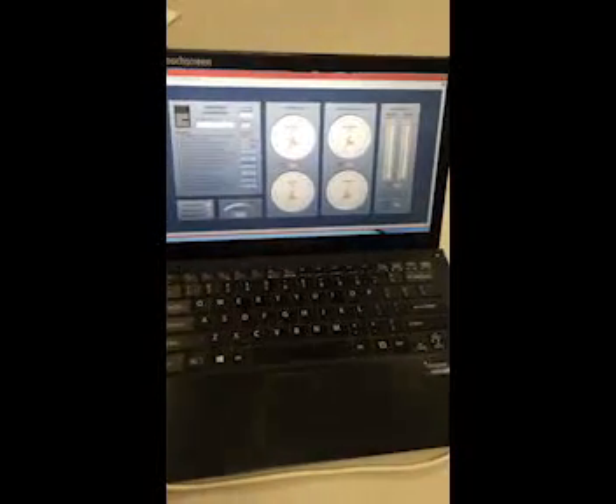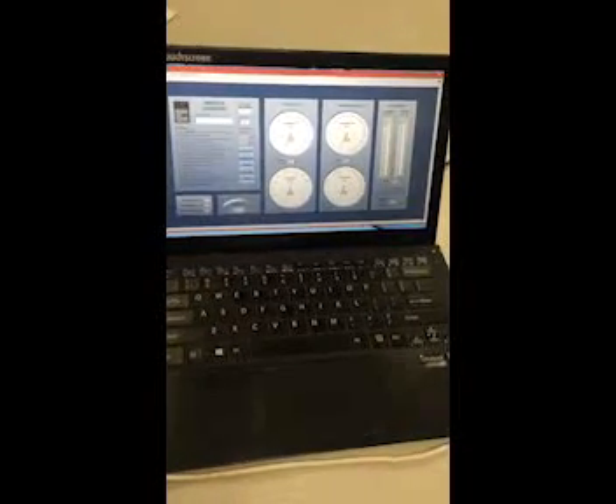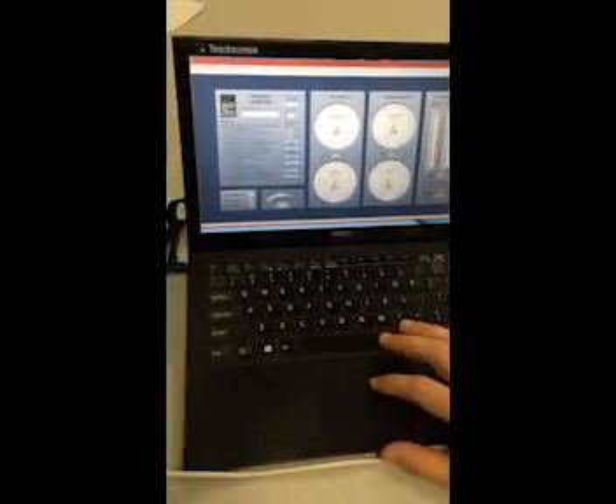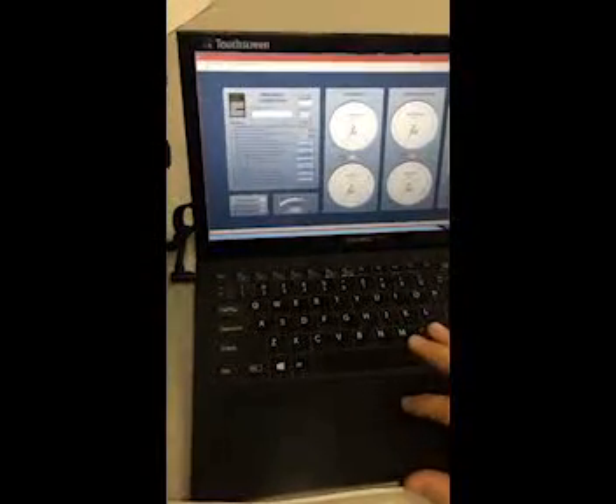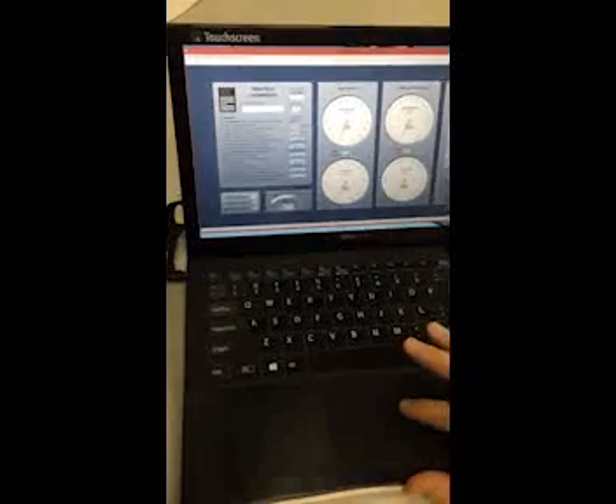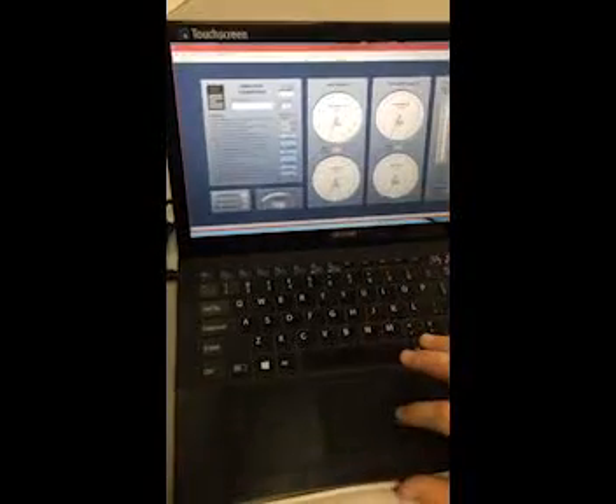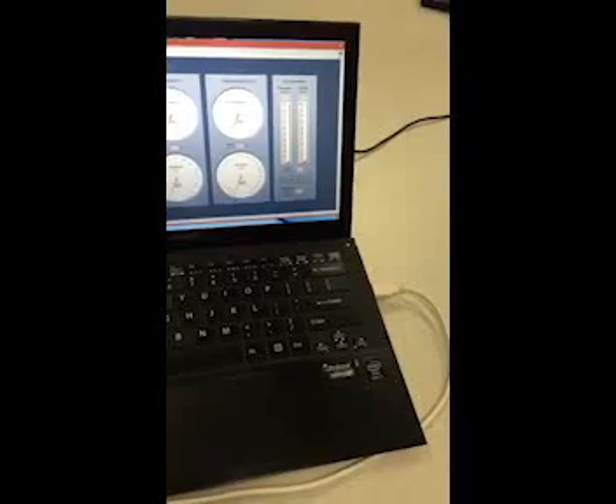The next step says that we're going to wait for the gas temperature to stabilize. The RTD inside of the test set, when the gas initially passes through there, will be a little bit colder. So we're going to wait for that to stabilize. And step number 9 tells us we're going to press calibrate temperature, which is located right here. Once we press the calibrate temperature, it'll make sure it's calibrated. You know it's done correctly. Again, on the right-hand side of your screen, this little red light here will actually turn green when it's calibrated correctly.